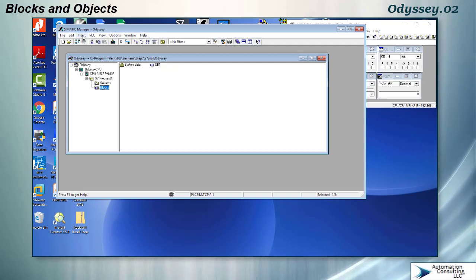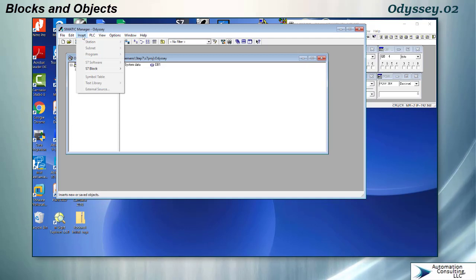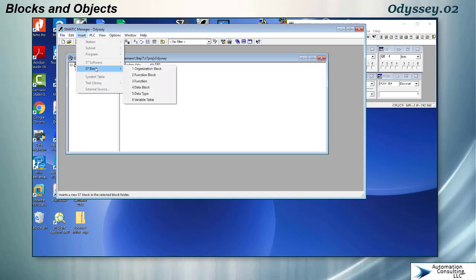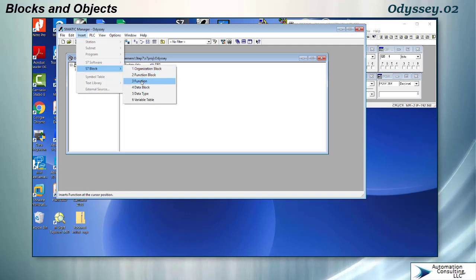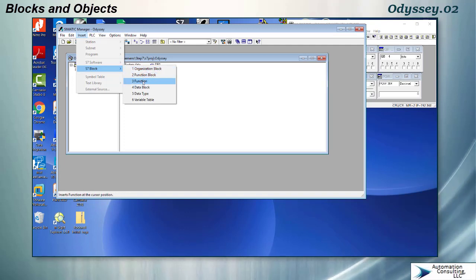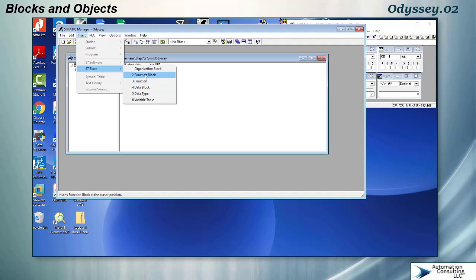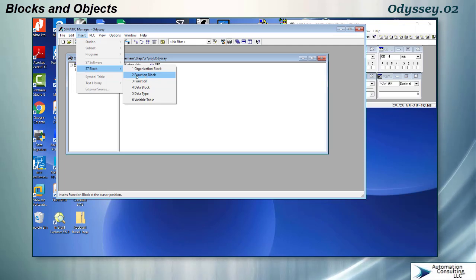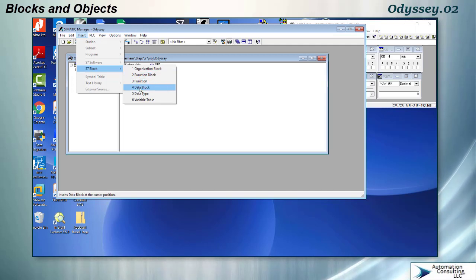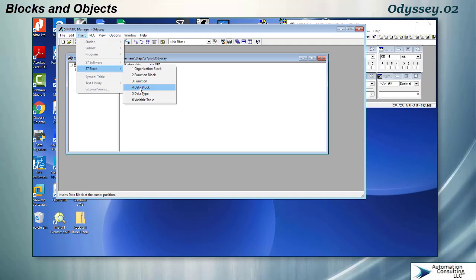A little bit about the different kinds of things that you can insert into a Siemens program. You have OBs or organizational blocks, you have functions and function blocks, they are different. A function is really just like a subroutine. A function block is like a subroutine with permanent memory assigned to it, that permanent memory is in the form of a data block. A data block is just a group of data, you can group different types of data and put it in your data blocks. It's a very useful feature of Siemens, a little bit different than the Allen Bradley stuff we've done.